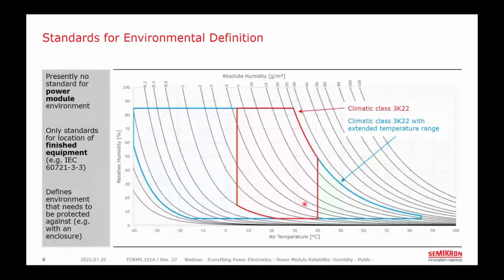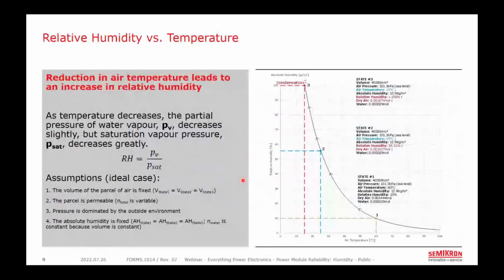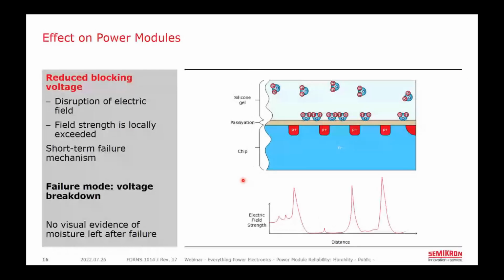Okay. And here's one I think you would be good to answer. The humidity condition causing overvoltage, could it reveal itself as a black mark on the transistor or diodes? We're talking about this failure mode here, where it's not corroding, but your electric field strength has been exceeded in an area. If you exceed the electric field strength, that means the chip is not able to block the voltage in that area. So if it's a 1200 volt device, and the blocking voltage strength has been reduced to 800 volts or whatnot, and you have a voltage higher than that, you would have an overvoltage condition and a short circuit there. That starts out as a little burn mark, and a short.